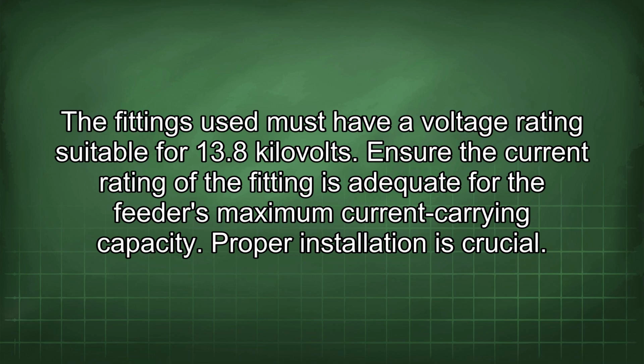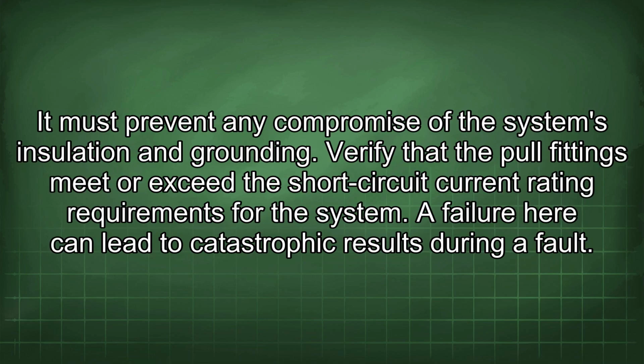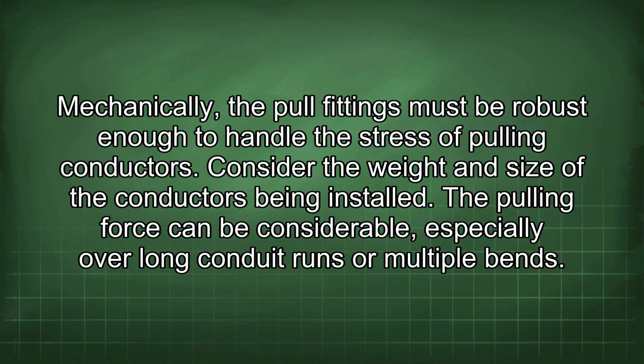Ensure the current rating of the fitting is adequate for the feeder's maximum current carrying capacity. Proper installation is crucial. It must prevent any compromise of the system's insulation and grounding. Verify that the pull fittings meet or exceed the short circuit current rating requirements for the system. A failure here can lead to catastrophic results during a fault. Mechanically, the pull fittings must be robust enough to handle the stress of pulling conductors. Consider the weight and size of the conductors being installed. The pulling force can be considerable, especially over long conduit runs or multiple bends.